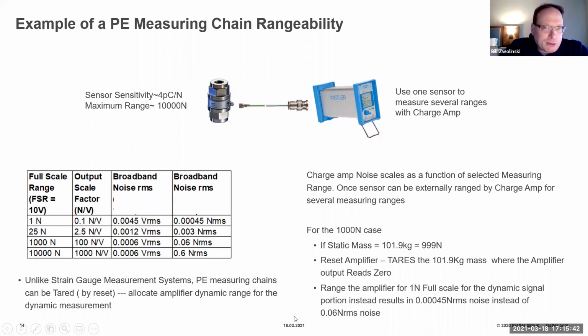A lot of times also in piezoelectric systems, you tare the measurement, meaning say you had, I don't know, 100 kilograms of mass acting upon a force sensor. You just reset the amplifier, the actual electrical measuring chain thinks you have zero mass on that force sensor, and now you just range the measuring chain based upon whatever event that you're trying to measure. So it gives you even better resolution because you can tare out any static masses, which is pretty powerful in terms of piezoelectrics.